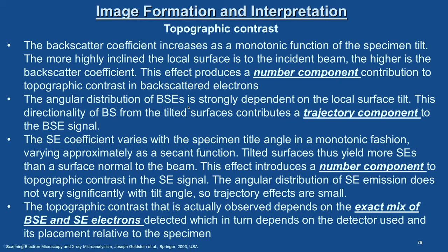The angular distribution of backscattered electrons is strongly dependent on local surface tilt, and this directionality from the tilted surface contributes a trajectory component to the BSE signal. The secondary electron coefficient varies with specimen tilt angle in a monotonic fashion, varying approximately as a secant function — in opposition to the cosine function for BSE. Tilted surfaces yield more secondary electrons than surfaces normal to the beam. This introduces a number component to the topographic contrast in the SE signal. The angular distribution of SE emission does not vary significantly with tilt angle, so trajectory effects are small for SE.